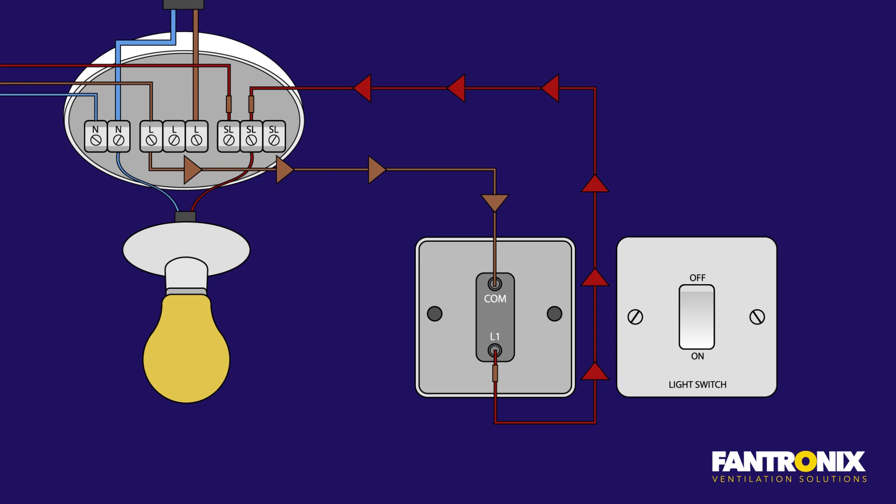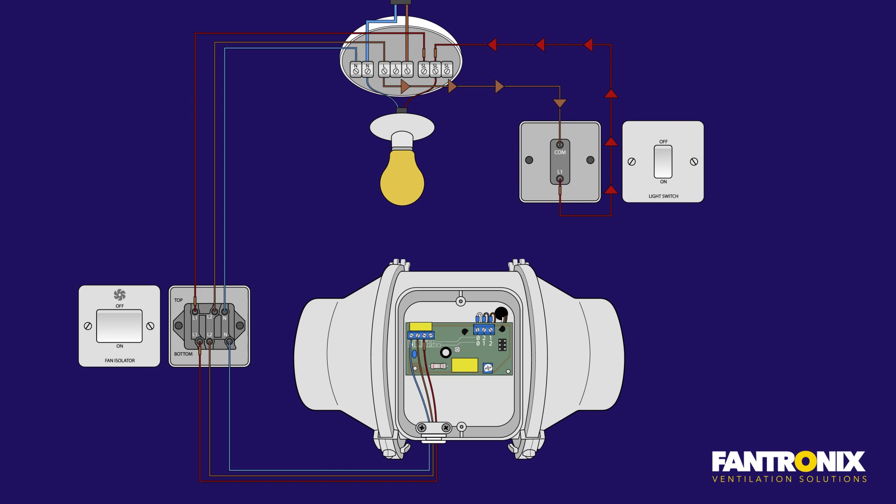When you switch the light on, the fan will come on. When you switch the light off, the fan will run on on its run-on timer, which is why we have the permanent live connection.